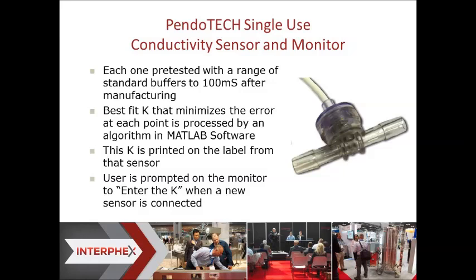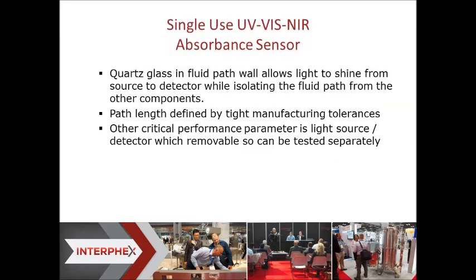Conductivity, it's a little more difficult. What we do after manufacturing is we pre-test each sensor with a range of standard buffers from 0 to 100 millisiemens, and we analyze through a MATLAB program the K factor that minimizes the error and makes the sensor the most accurate. That K is printed on a label, and when you connect the sensor to your monitor, it prompts the user to enter the K factor, and that's what gives you the accuracy. The single-use absorbance sensor, the only factor here really is the path length. In order to accurately determine the final measurement that you're looking for, you need to have a consistent path length. And being that ours is a molded part and it's manufactured, the path length is consistent.